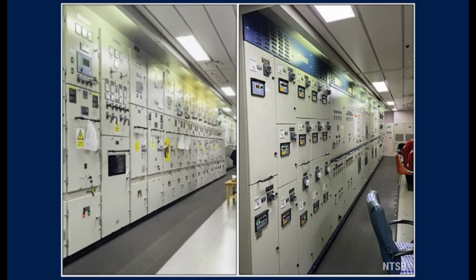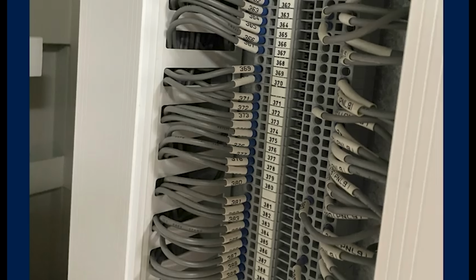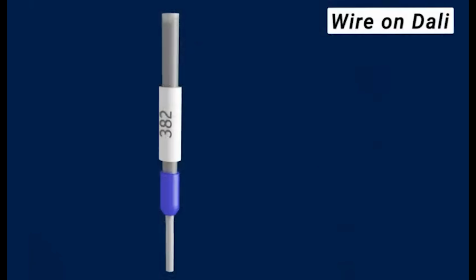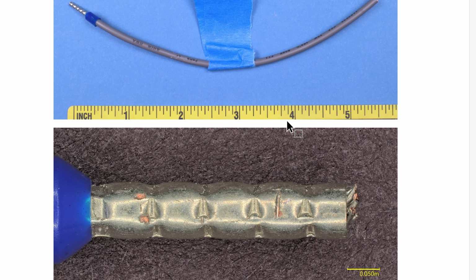The motor vessel Dali's electrical system distributes the power and control signals throughout the entire ship. And it does it through these blocks that you see right here on the screen with wires that connect into these terminal blocks. The wires on the Dali were terminated with these metal sleeves called ferrules that allowed for easier assembly into the terminal blocks. So for example, here's a sample piece of the wire that they took from that same terminal block, and there's your ferrule, your metal ferrule, and there's the blue plastic cap that goes over it.